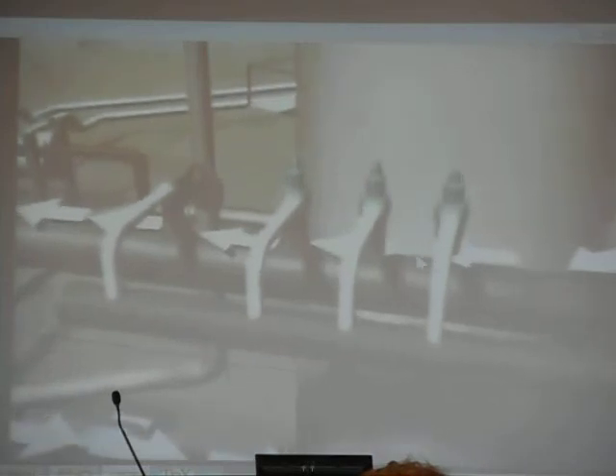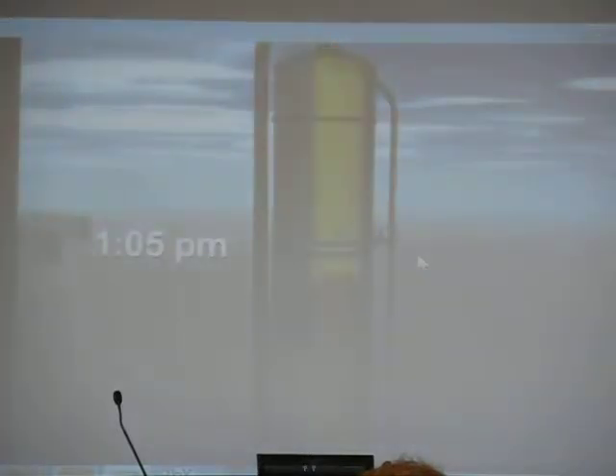Around 12:40 p.m., a high-pressure alarm was activated. Two burners were turned off in the furnace to lower the temperature. The valve specified in the procedures for controlling pressure didn't work, so an operator used a manual chain valve to vent gases to the blow-down drum and into the atmosphere. At about 1 p.m., operators opened the valve to send liquid from the bottom of the tower to storage tanks. But the liquid at the bottom was very hot, and as it exited through the heat exchanger, it suddenly raised the temperature of the feed going into the tower by over 150 degrees. By 1:05 p.m., the liquid entering the tower was beginning to boil and expand, causing the level inside the tower to increase further.